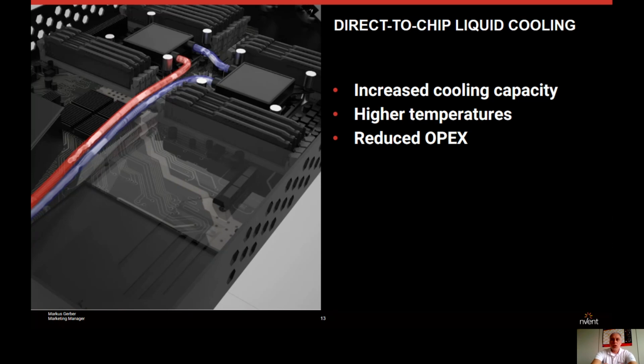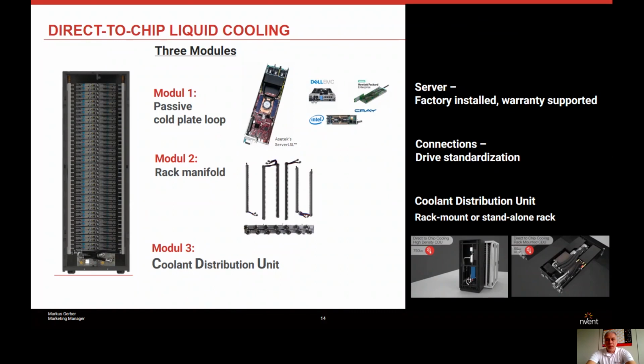So now you would probably ask the question, if I can use higher temperatures, if the equipment is available, how does it build up? I see three modules. The first module is the server. As already mentioned, there is a cold plate on the server. And as of today, the main server manufacturers already offer different types of servers with a pre-installed cold plate. Then this server is connected to a rack manifold on the rear side. This works basically like a PDU, and then it transfers liquid to the different servers.